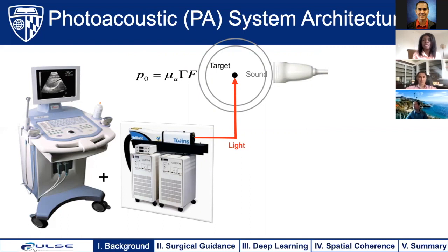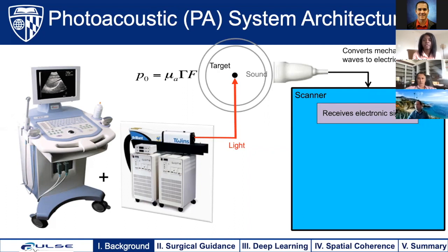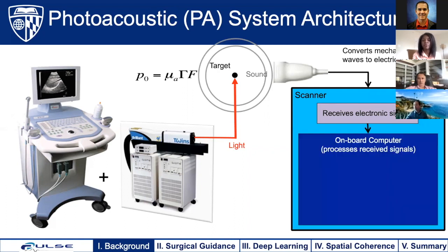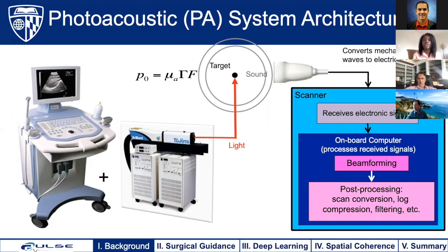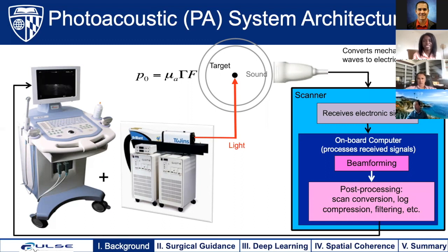So I generate this initial pressure distribution that propagates toward the probe, and then the same piezoelectric elements that are used to convert mechanical pressure waves into electrical signals for ultrasound images can do the same process to create photoacoustic images. The process is fairly similar to what you saw in the previous slide, where these signals are sent to a scanner, which receives the signals and sends them to an onboard computer. We see again this critical beamforming step that's at the heart of both ultrasound and photoacoustic imaging. Then we would do some additional post-processing, and finally the photoacoustic image is ready for display on the monitor.